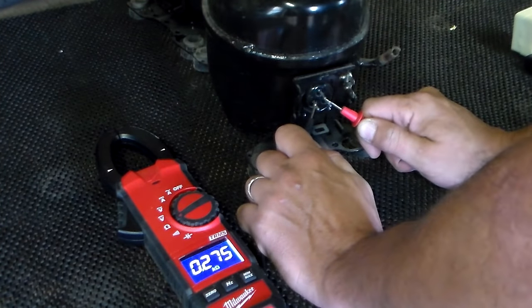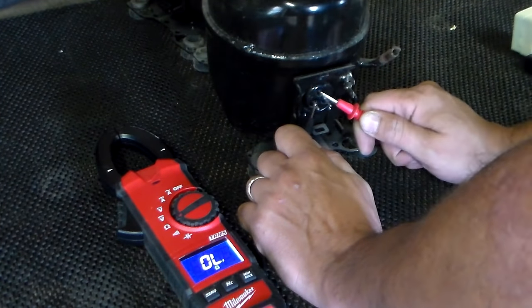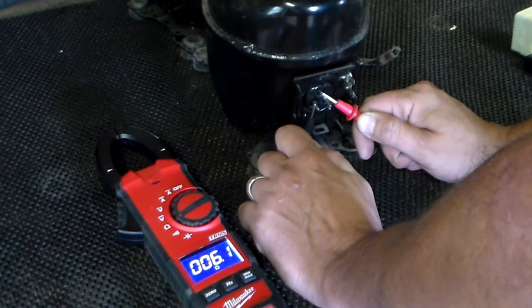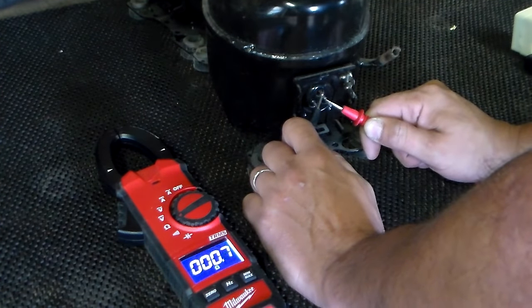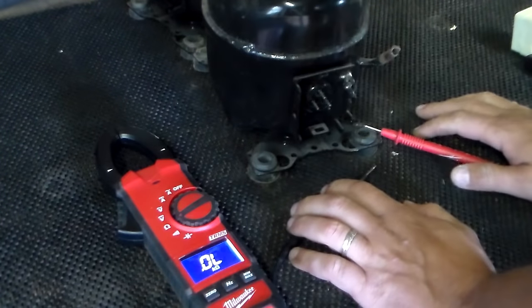So I'm going to use one that has been used for a while. Here's one that's used, so we're going to do the same test. Across the bottom — ten. From the top to the bottom left, we're getting six. And from the top to the bottom right, about four. And these two compressors are perfectly fine.